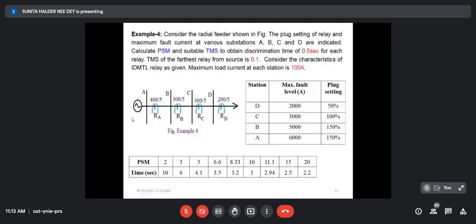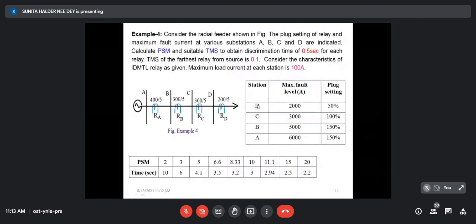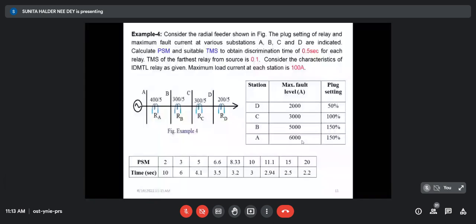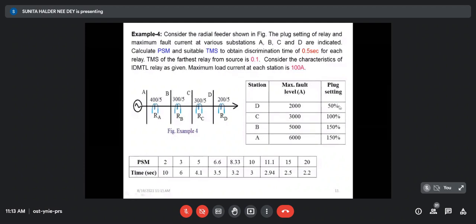There are four relays: A, B, C, D. The fault current at different fault terminals is given — the fault level at each bus. These are the different fault levels calculated, and plug setting is also given for the relay. We have to set the relay — what will be the plug setting multiplier and time multiplier setting — to obtain a discrimination time of 0.5 second.